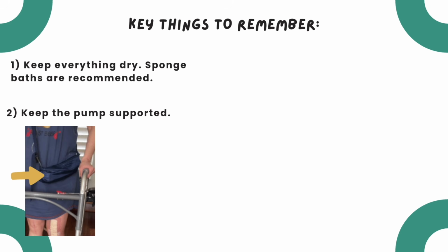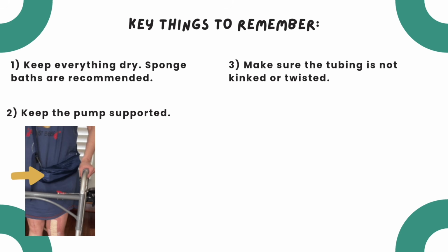Your team will provide a sling pouch to carry the pump. Keep the pump at or above the level of the catheter site, for example, at waist height or in the sling pouch. This is important because if the pump hangs below the catheter, gravity can reduce the flow of medication. Don't let the pump drag on the catheter tubing, as this may pull the catheter out. Third, make sure the tubing connecting the pump to the catheter is not kinked, twisted, or clamped off at any point. A kink can slow or stop the medication flow.